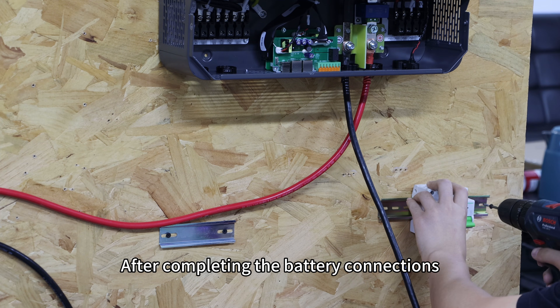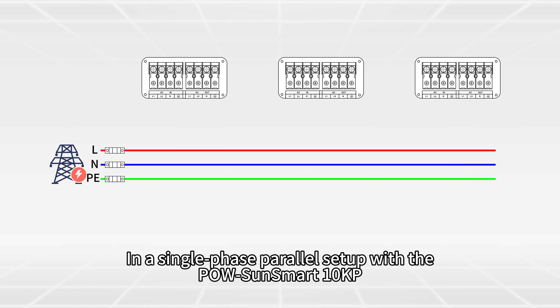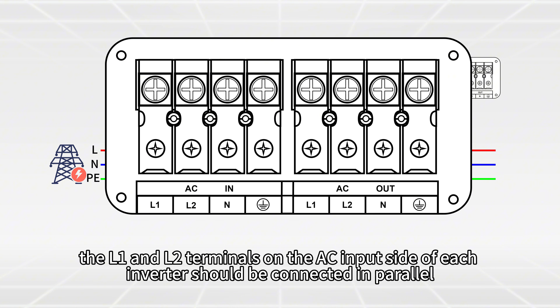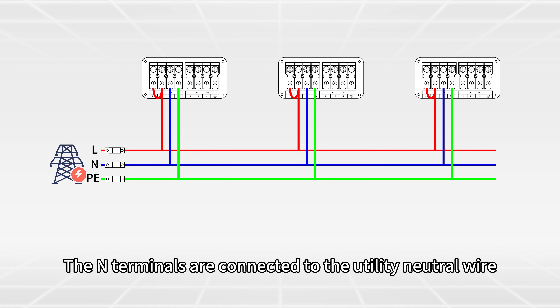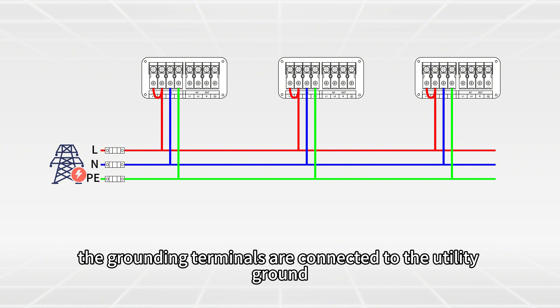After completing the battery connections, move on to the AC wiring. In a single-phase parallel setup with the POW-SunSmart 10KP, the L1 and L2 terminals on the AC input side of each inverter should be connected in parallel. From this point, connect the output to the live wire of the utility. The neutral terminals are connected to the utility neutral wire, and the grounding terminals are connected to the utility ground.